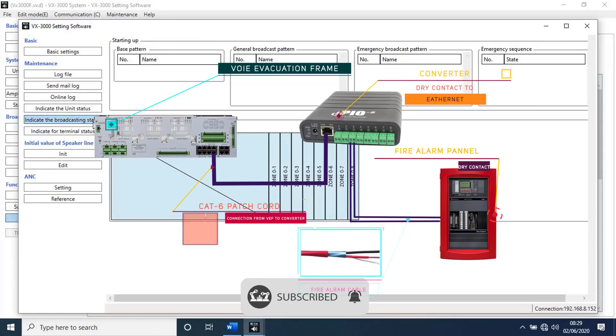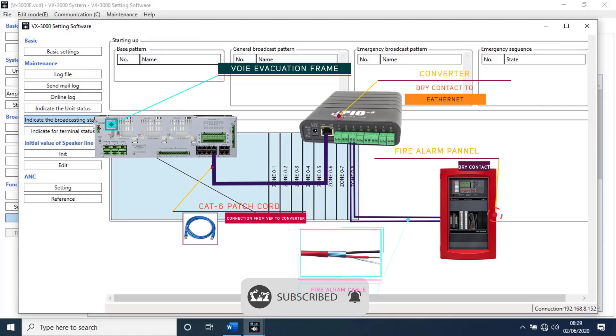Here is the question: how to give fire alarm signal to unit? Because we don't have any input dry contact terminals, but we have control input which is RJ45 jack module. We have to convert the dry contact to ethernet through converter.